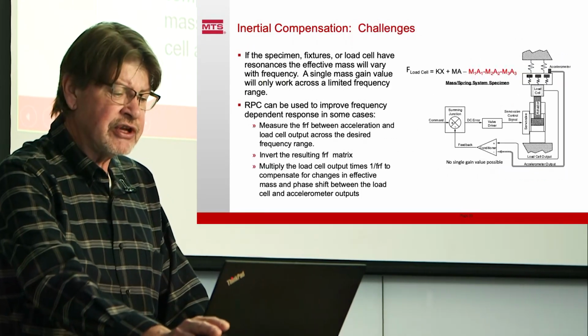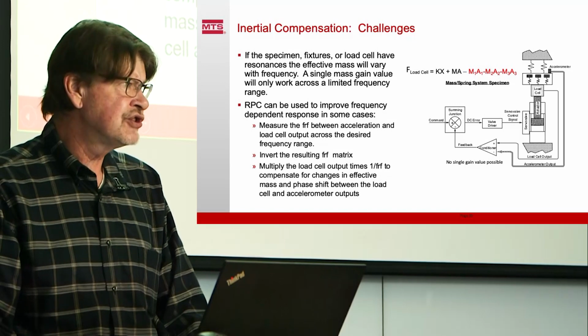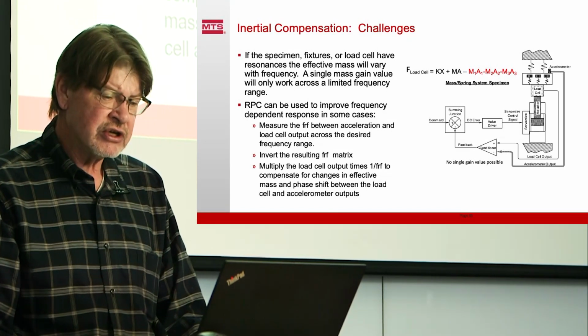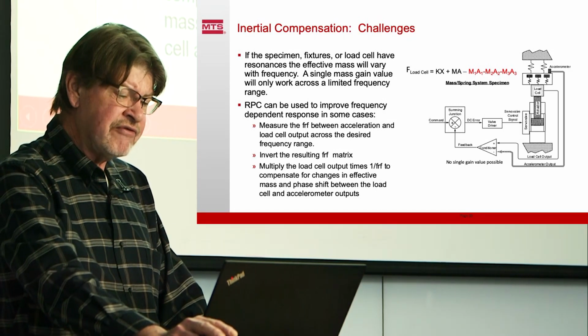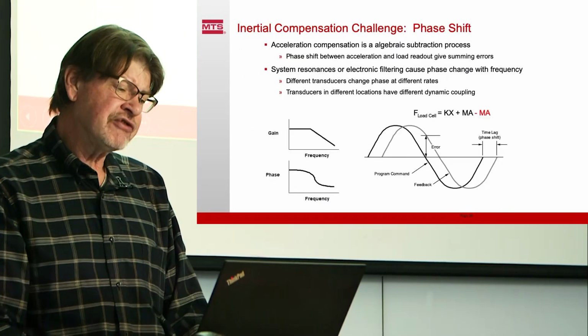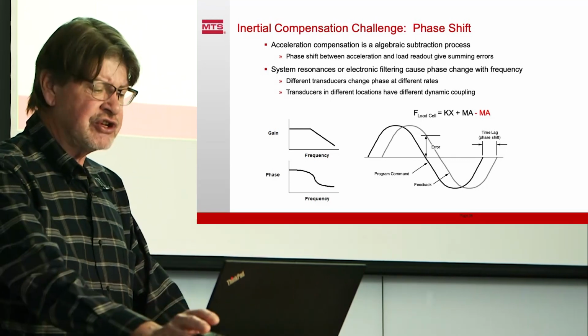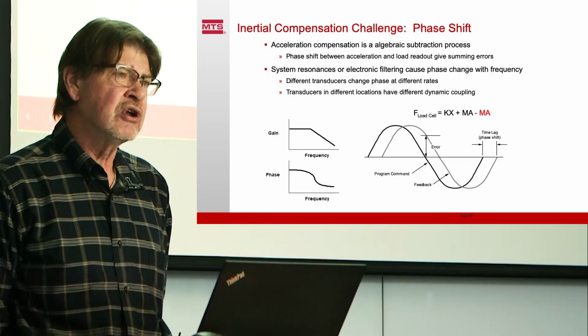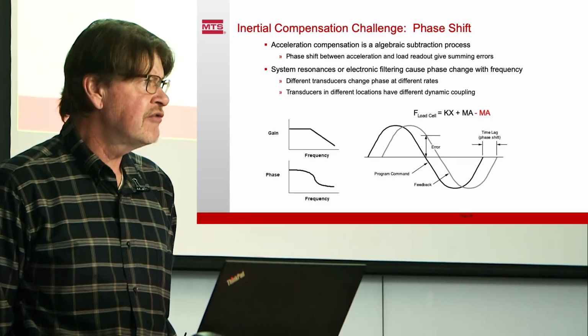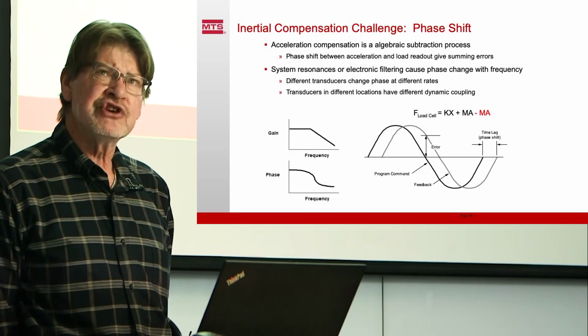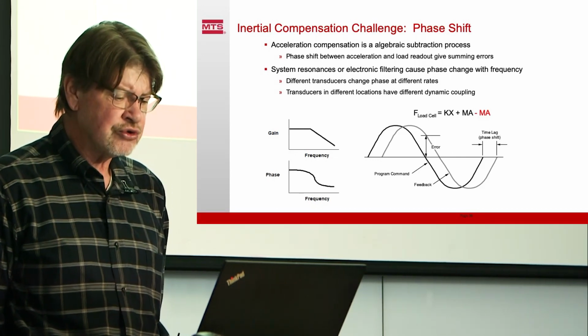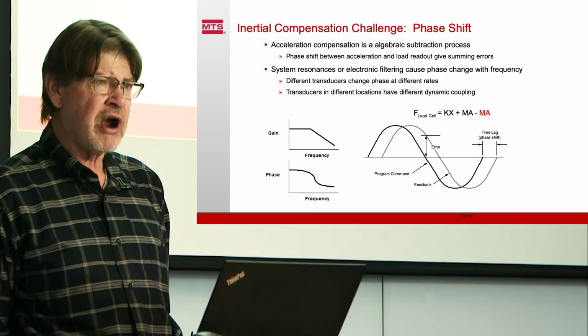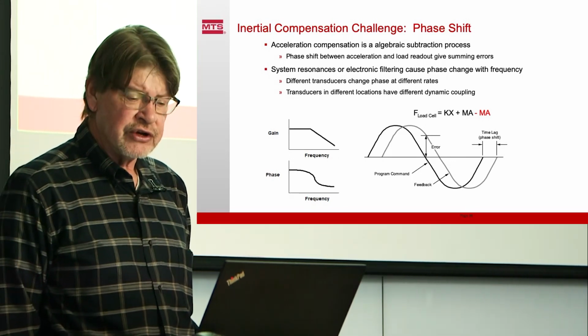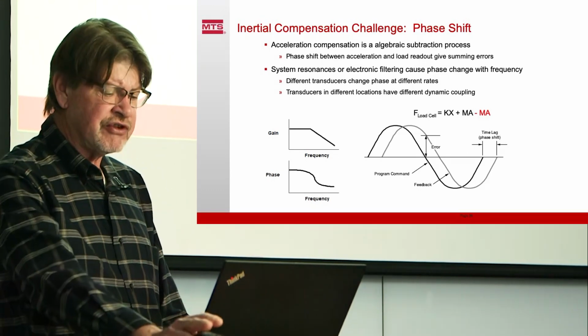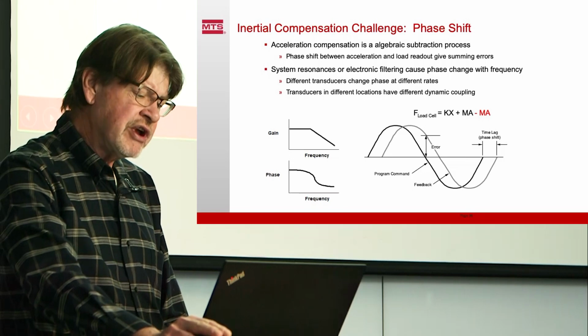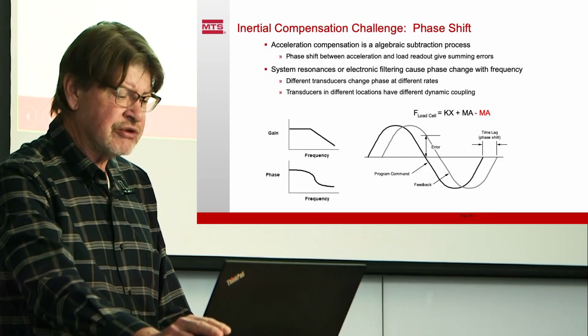There are limits, however. For one thing, you've got to have a single contiguous mass with no resonances anywhere near the frequency range of operation. You've got to have a pretty well-behaved system and good clean waveforms. You have to be careful about phase shift or filtering, especially when you get into summing these transducers. For example, if you're trying to sum an accelerometer and a load cell, they likely have different natural frequencies. That means as you start to run at higher frequencies, you're going to phase shift and amplitude shift the signals between those two. Then if you try an algebraic sum, you're going to subtract the ma from the existing ma. Even small phase lags give you very large errors in the algebraic summing. So we have to be very careful in what cases this actually gives us the accuracy that we want.